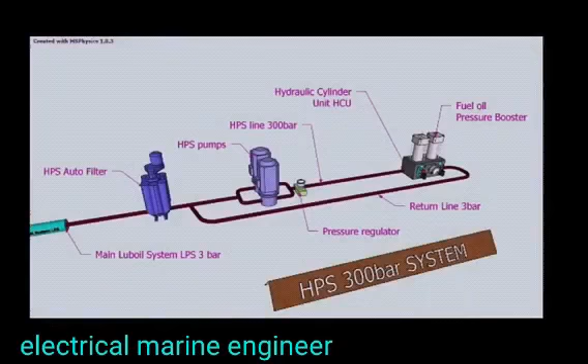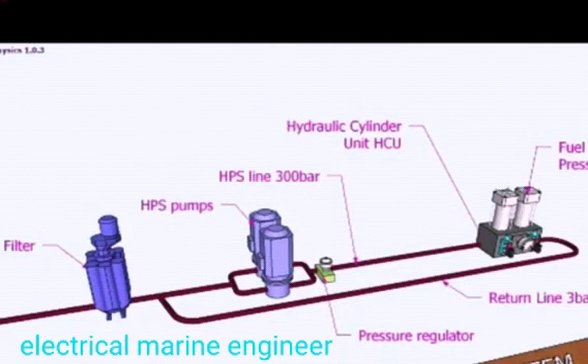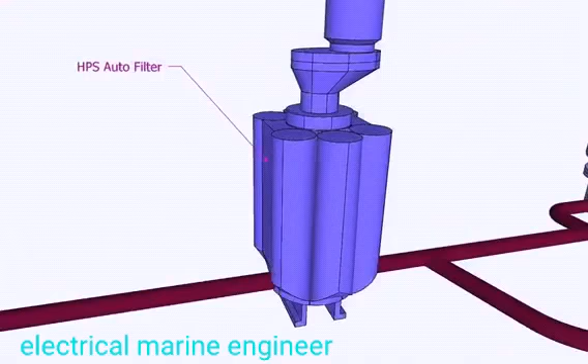Actually, the MEB engine concept is the use of a mechanical hydraulic system for actuation of fuel injection pumps, which are electronically controlled by a computer based control system, and for that, main system lube oil is used as the hydraulic medium.